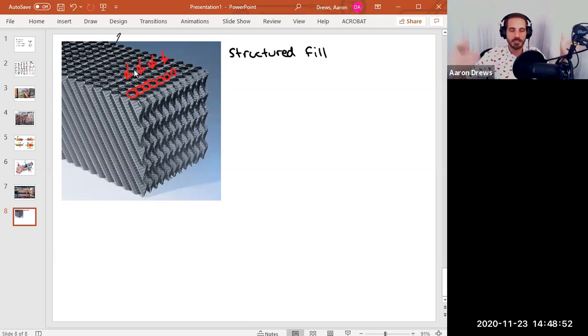It sort of falls down and it hits the, imagine we've kind of got a cutaway here, right? It falls down, it hits one of these ridges, and then it kind of runs its way down the ridges this way. And then the sheet that's right next to it has ridges going the other way. So the water is falling sort of in a crisscross direction going down. And meanwhile, the air is coming up through the entire system, but you can't get in there and clean it out. These things are plastic welded together. And so they're kind of stuck.